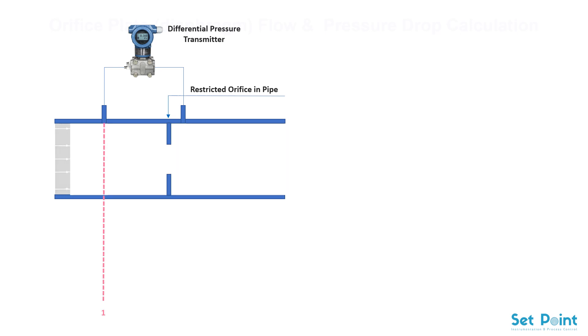Downstream of section 1, streamlines are converging towards the orifice plate, which indicates that velocities are increasing due to reduction in area. Fluid stream continuously accelerates beyond the orifice plate until a point where area of fluid stream reduces to a minimum value. This minimum area at section 2 is known as vena contracta.